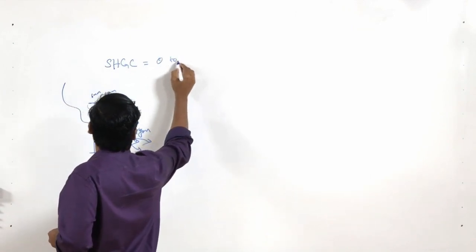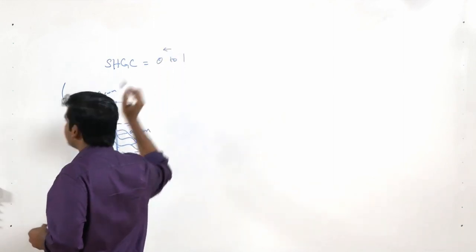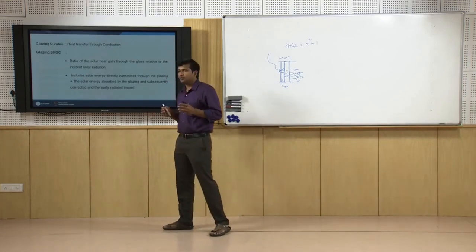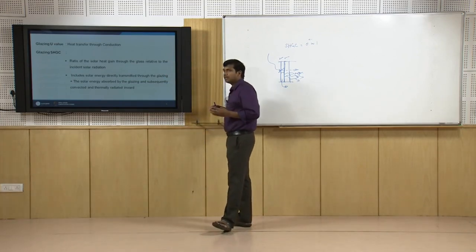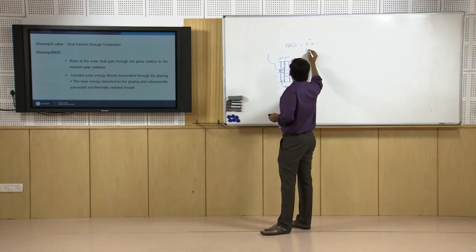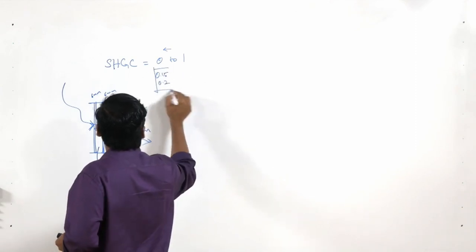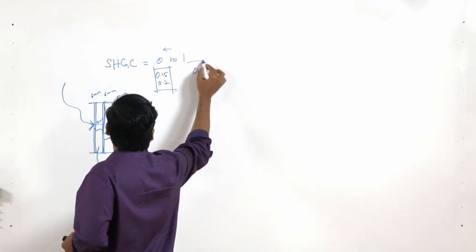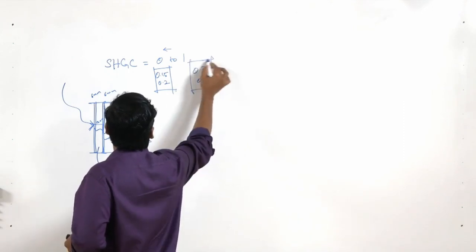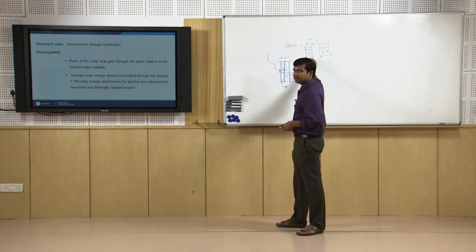Effectively this is expressed using SHGC or solar heat gain coefficient, ranging from 0 to 1. The closer to 0, the more efficient the glazing system. Highly efficient low-e (low emissive) glazing systems will have SHGC values closer to 0.15 or 0.2, whereas a single clear glazing system may have SHGC of 0.7 or 0.8, meaning more radiant heat is transmitted into the space.